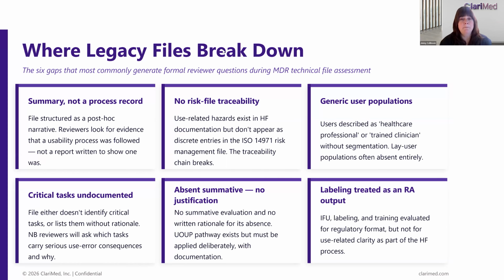And then, as I mentioned previously, labelling needs to be very much part of that human factors process. It needs to be pulled in, assessed, made sure that any labelling IFUs are appropriate for that user group you've identified, and making sure it's part of your usability engineering file. Now, I've mentioned this a number of times, user interface of unknown provenance. So the next slide, we'll just go into that a little bit more, because it's a key step.